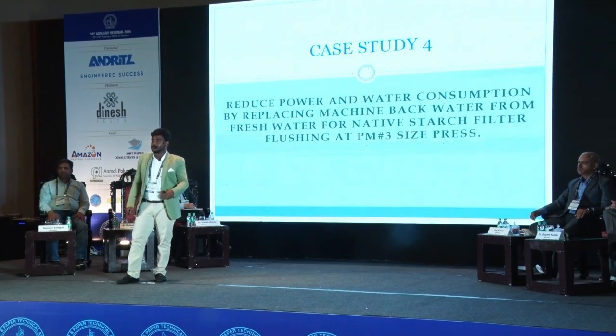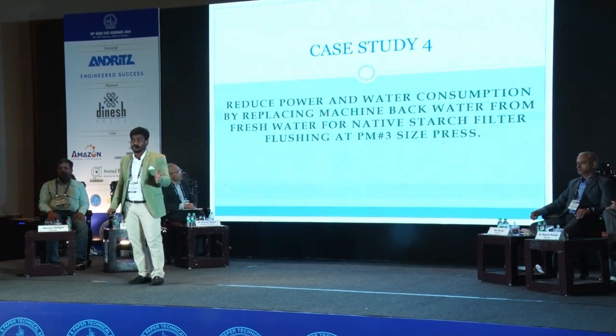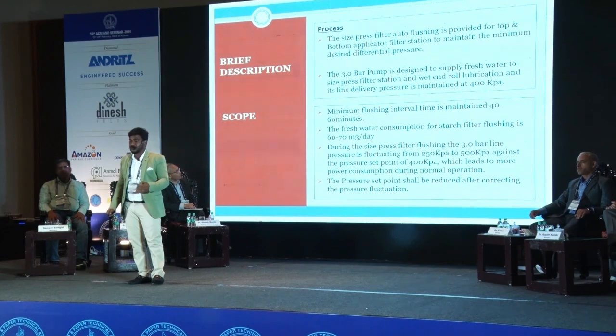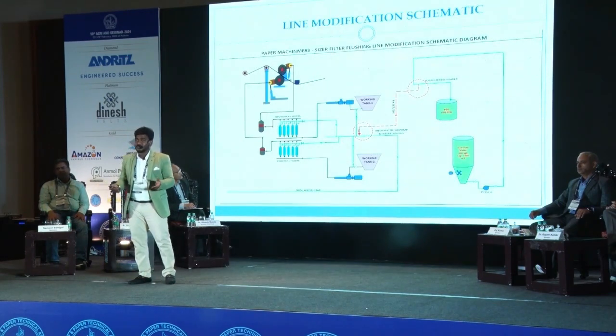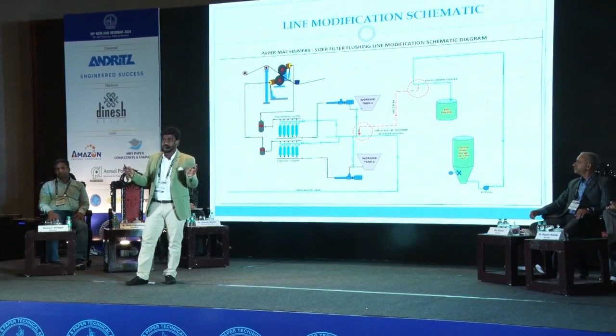And our final case study is reducing water and power consumption by replacing fresh water in the size press filter flushing. So I'll go a little bit faster. We have size press applicators equipped with 5 filters, and these filters are auto flushed once every 40 to 50 minutes as per the starch quality and the required DP. And we are using 3 bar fresh water for this filter flushing. It is observed that whenever flushing occurs, there is pressure deviation in the 3 bar delivery. To avoid the deviation, we always keep the set point higher, up to 400 to 450 kPa, in the delivery to avoid the fluctuation.